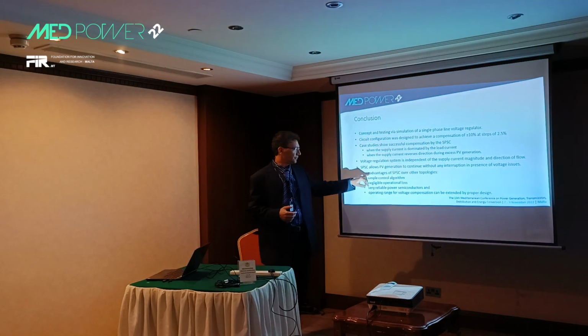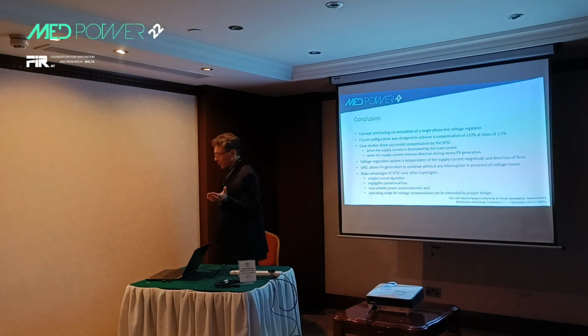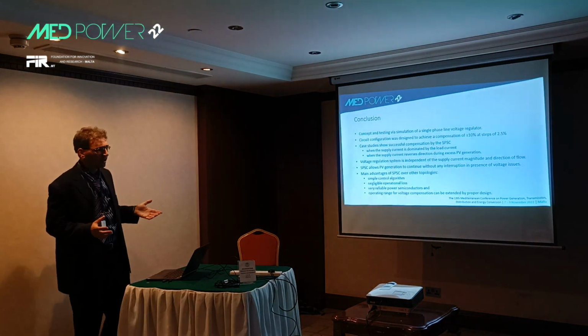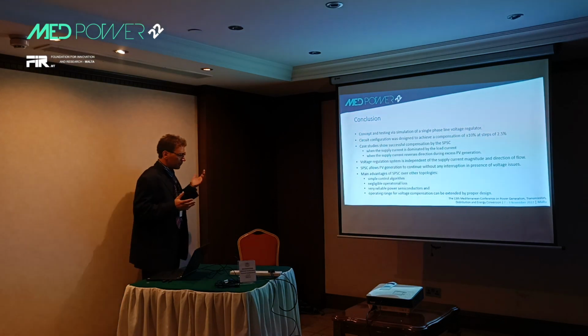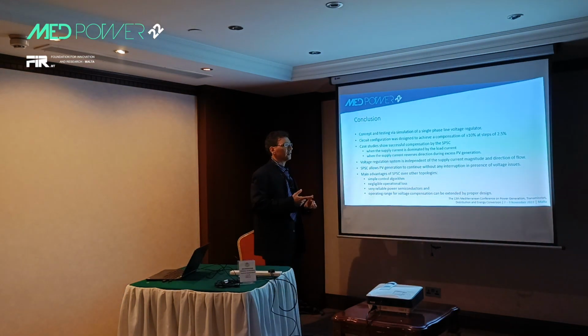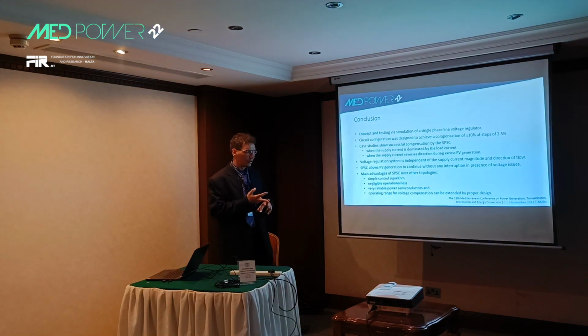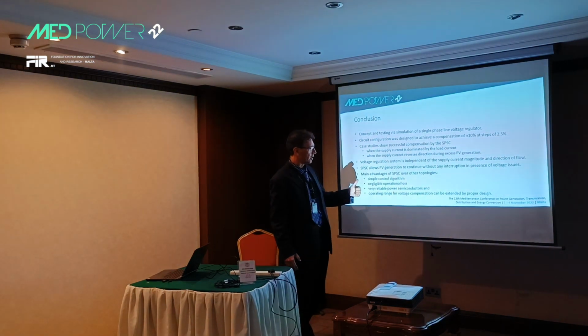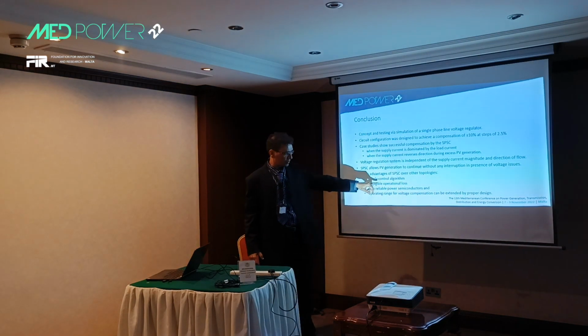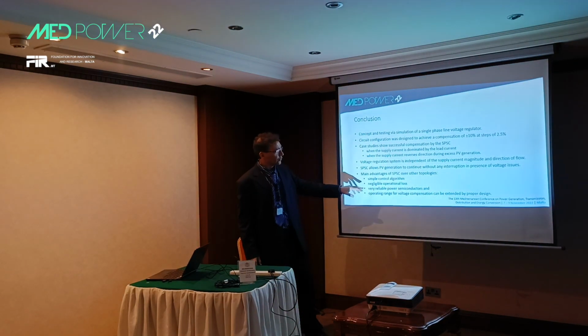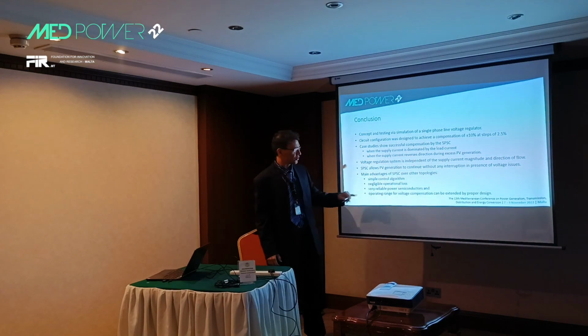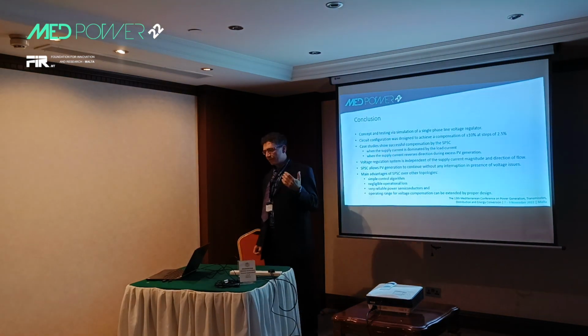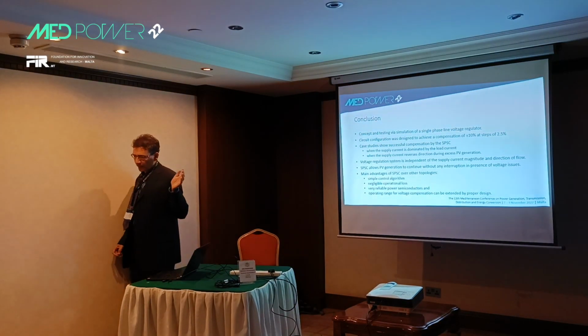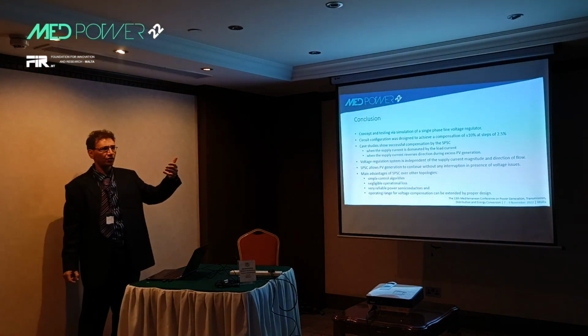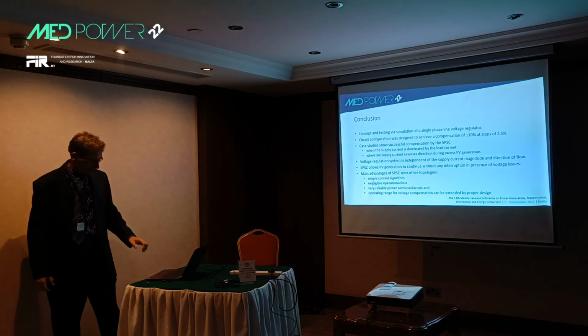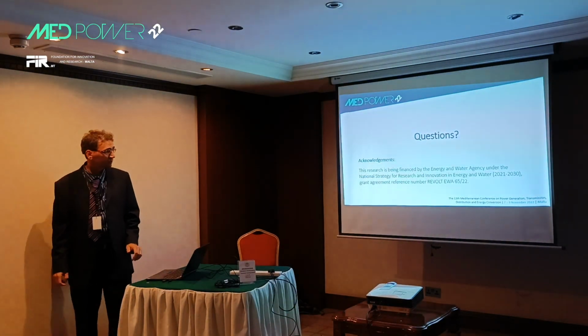And why did we go for this topology? Why didn't we use an active filter, for example? Active filters are quite well established. The problem with active filters is they are expensive, they are very difficult to control, and unfortunately they are not so efficient. So here we went for a simple control algorithm, very low, negligible operational losses, reliable semiconductors, thyristors, and also this type of circuit. And if you want to increase the plus or minus 10%, all you have to do is add another series compensation coil. So, thank you very much.